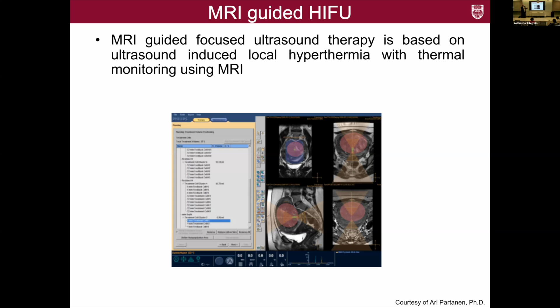I will show you. The MRI-guided HIFU therapy is based on local hyperthermia, and you can see here nicely, we can now define the volume that we want to treat, and the computer then calculates the treatment volume and the treatment time, similar to radiation therapy. So we have an MRI with a HIFU device embedded in the MRI table. Then we have a 3D anatomical scan, like in a regular MRI suite. And we also have additional temperature mapping, so we try to determine how high the temperature is in a certain tissue. Then it goes to the ultrasound driving system, and this is what I talked about: the phased array transducer that we use in the patient table, and you can use steering to locate the beam in different locations.